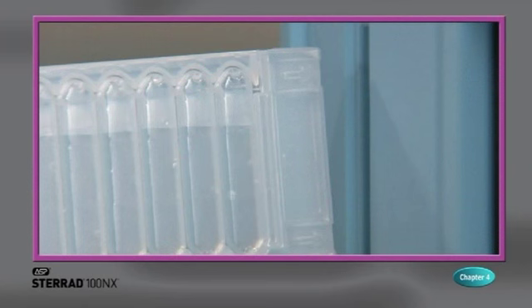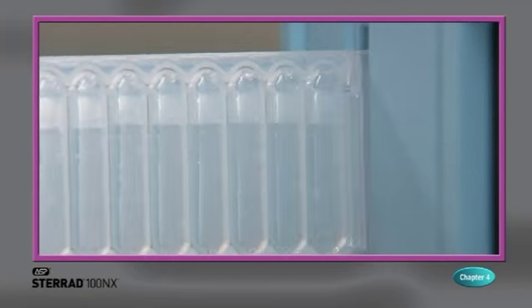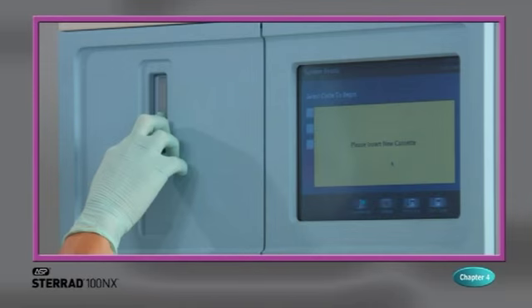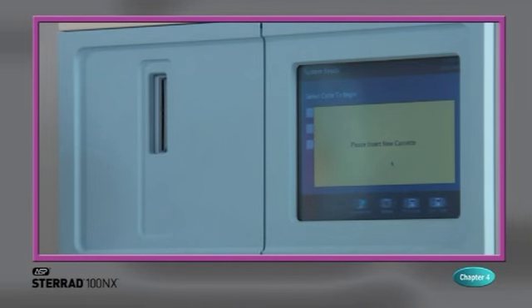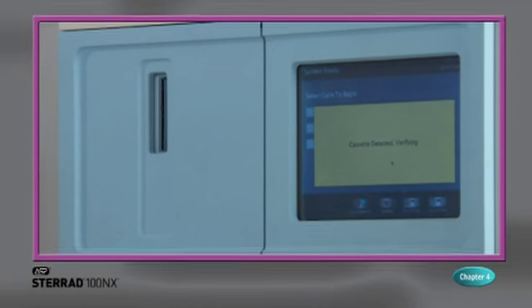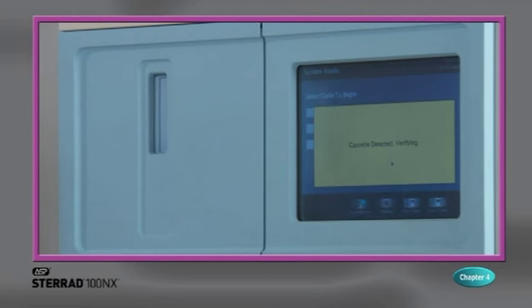Position the cassette so that the arrows are pointing towards the sterilizer. Insert the cassette into the cassette slot until it stops moving. Do not use force to push the cassette into the machine. After a slight pause, the sterilizer pulls the cassette through the slot and the slot door closes. Cassette loading is now complete.